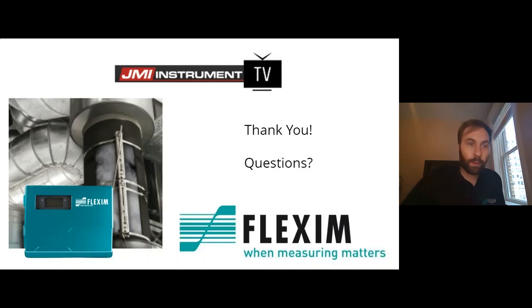We have our first question in the chat. Using PVC pipe, is it possible to measure lower pressures? Steve? Yes, so PVC, polypropylene, plastic piping, anything that's not metallic, you can measure low pressures, all the way down to atmospheric, as a matter of fact. We use polypropylene for flare gas measurement off of tank flares. Non-metallic, PVC is basically a noise insulator, so it doesn't resonate that noise like a metal pipe would.